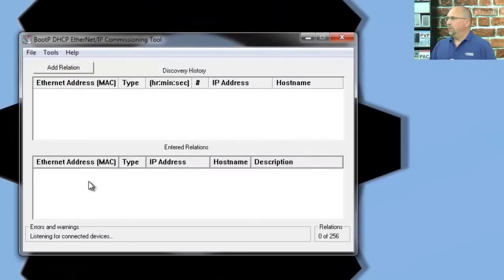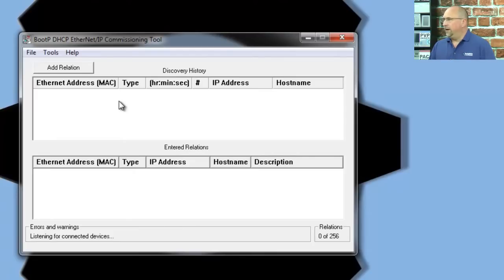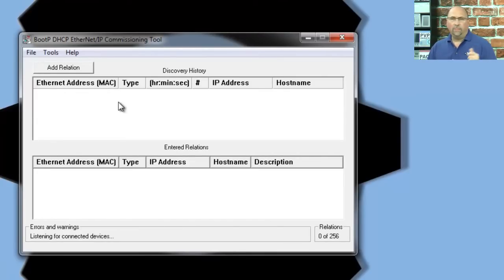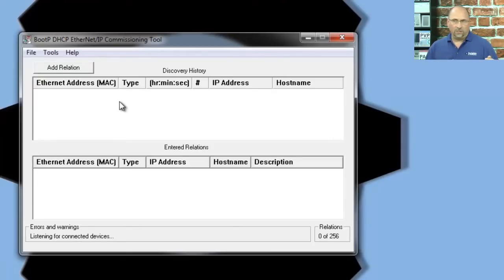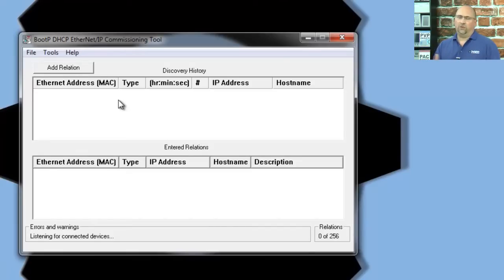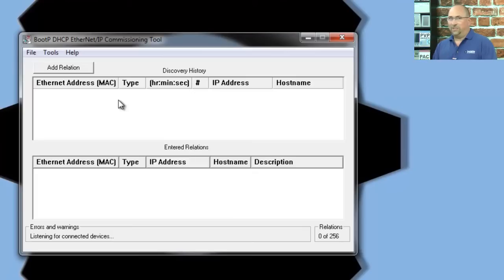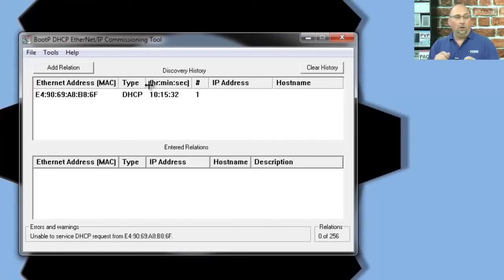So, let's open that up, and here in this top window, we should see both of those PLCs ask for IP addresses. And we want to make sure that we know what their MAC address is to match it up to the PLC, because sometimes your computer's Bluetooth or wireless card may be asking for an address as well, and you don't want to assign your computer or maybe somebody else's computer an address accidentally. You want to make sure the address is assigned to your PLC.